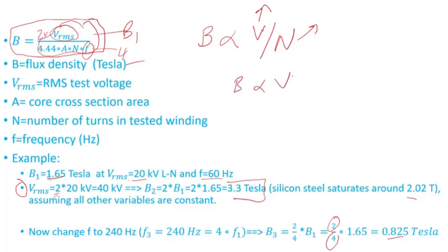...you must increase the frequency. Because the number of turns are fixed, you can't change them unless you redesign. But since I'm just making the changes during the test, I increase the voltage, that means I have to increase frequency. So that's why frequency is increased during the induced voltage test.